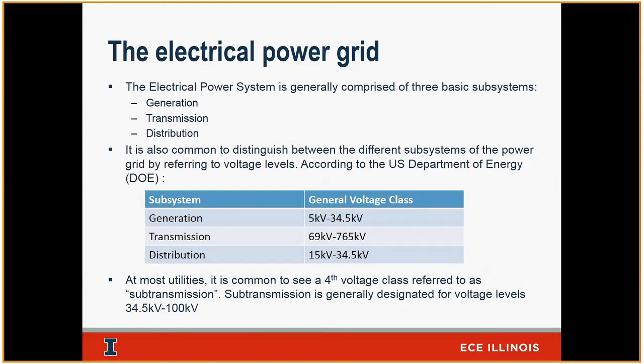Sub-transmission level in many utilities is anything 30 kV and above, or 34 kV and above, all the way to 100 kV. So between 34 kV and 100 kV is considered a category we call sub-transmission. And then 34 kV and below is considered the distribution defining voltage.